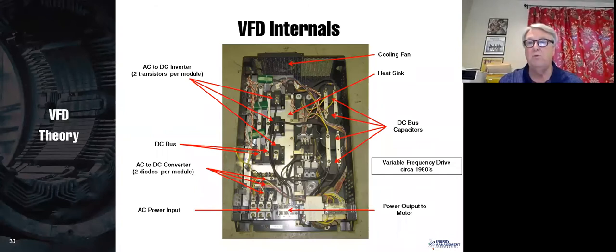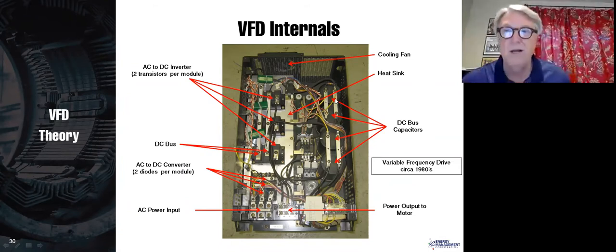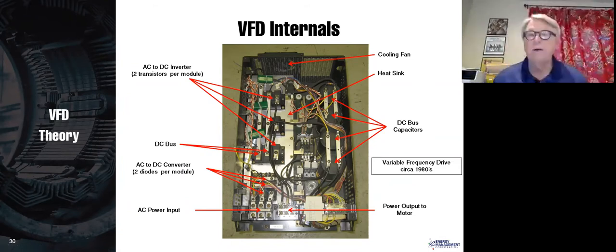But we have a lot of ripple on the DC, and therefore we have to have these capacitors. In this case, we have 4 capacitors, but they just act like one capacitor. And you may have 1 capacitor in a drive, you may have 12 capacitors in a drive. It just depends upon how big the capacitors are and how much capacitance you need. By the way, if those capacitors are functioning correctly and the converter is functioning correctly, you shouldn't get more than about 3 volts ripple on the DC bus.